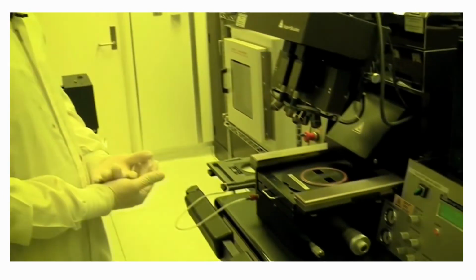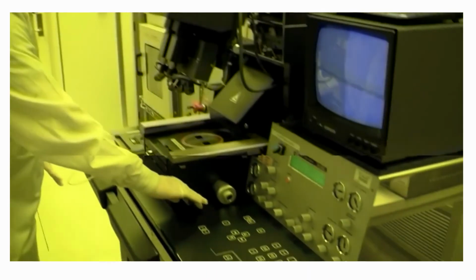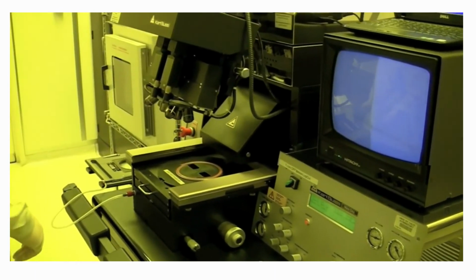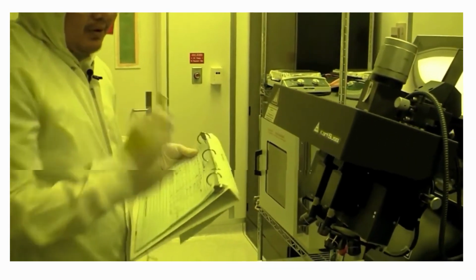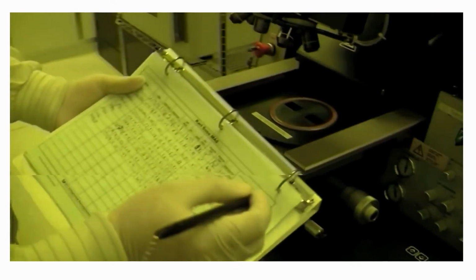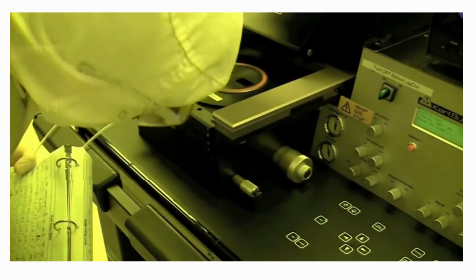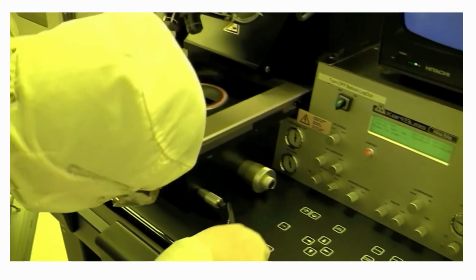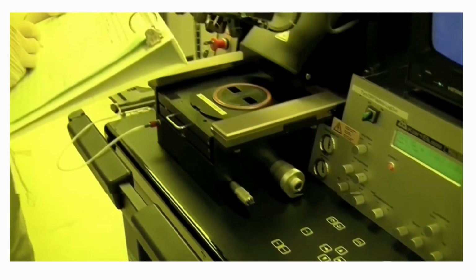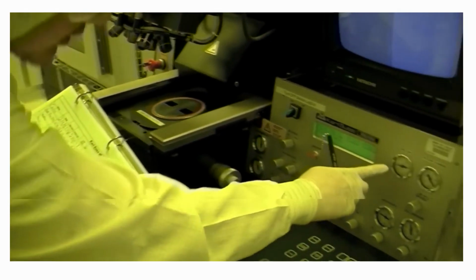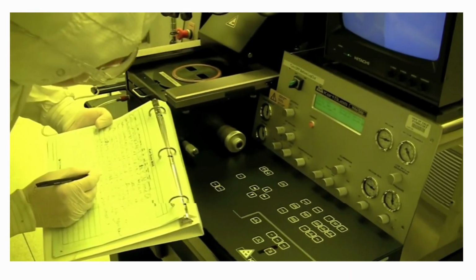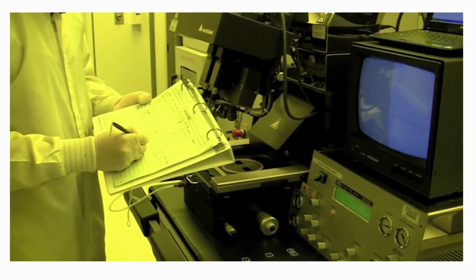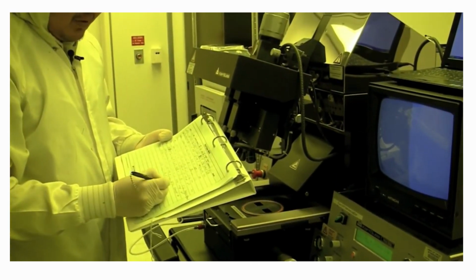So now we're ready to turn the system off. So we want to make sure everything's in the standby position that you started the machine with. And then before you turn it off, you want to make sure you write in the logbook the different parameters. So the compressed air is about 4.9. The nitrogen is about 1.65. The vacuum is about negative 0.86. We used a 4-inch silicon wafer, and we did a 25-second exposure.